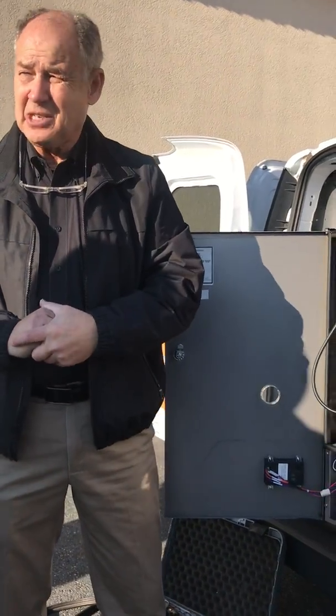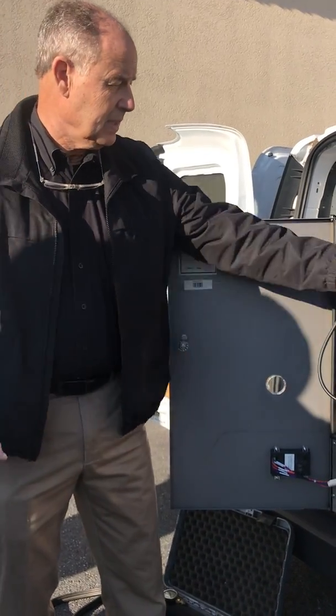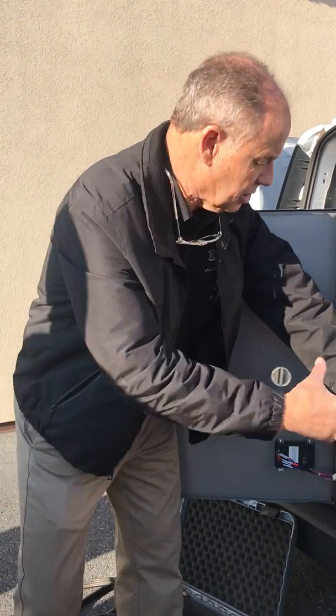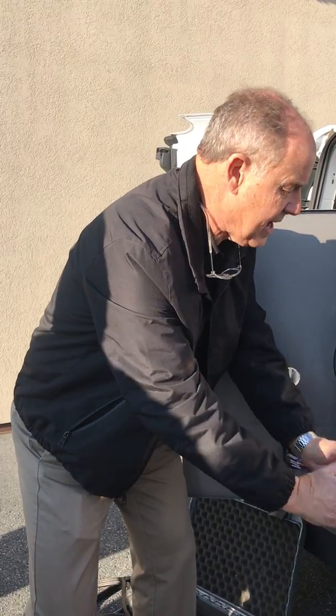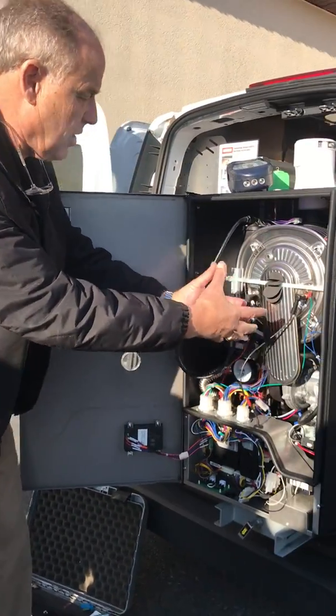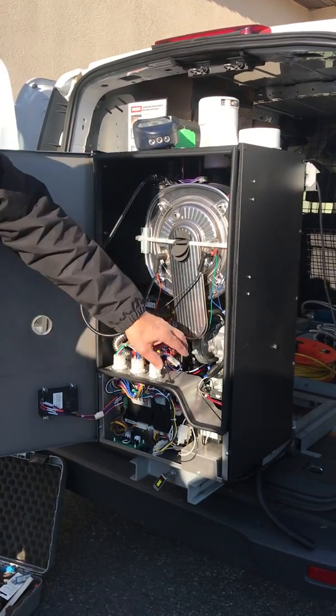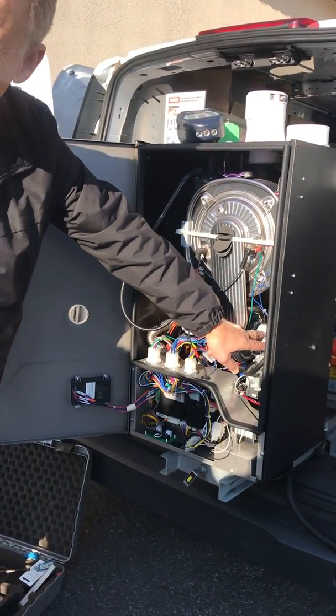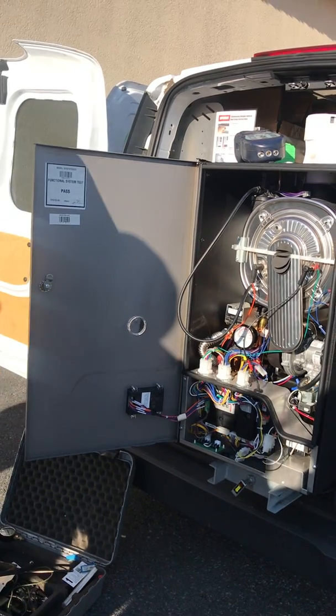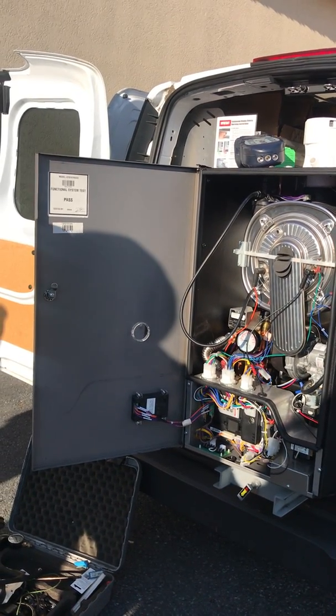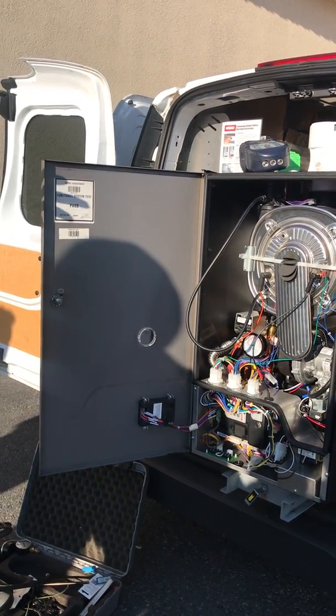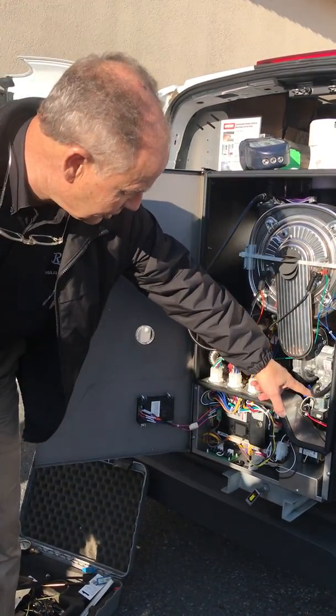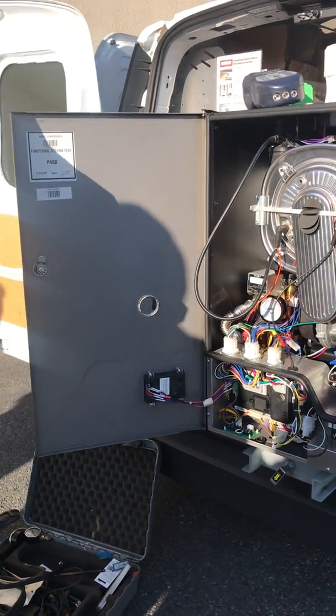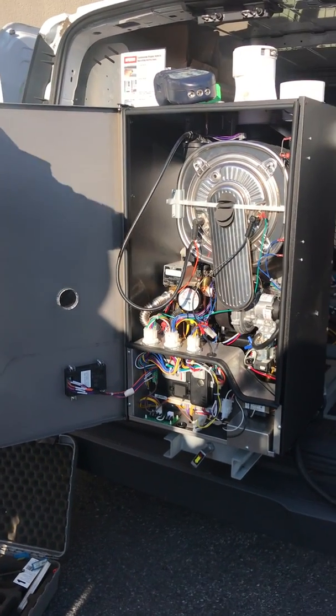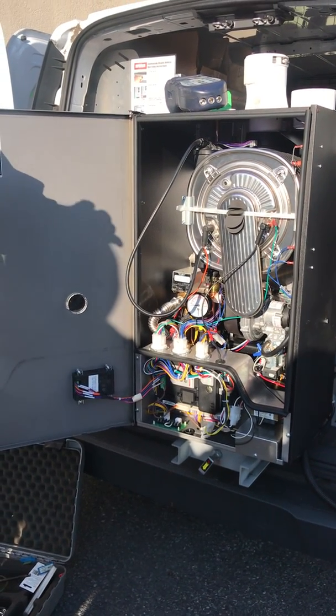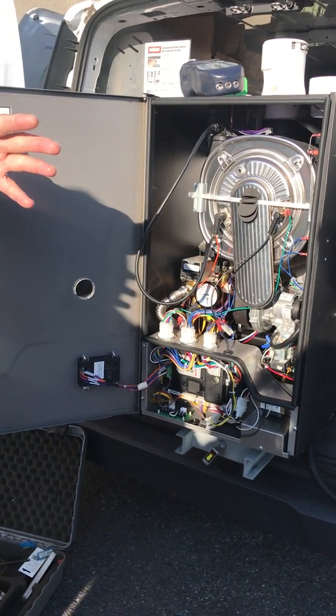But when you get a job and you need to convert it from natural to propane, these 4 nuts are going to come out. You're going to loosen the union. The nut's going to drop down. I can take all my wires off and I can pull this whole thing out. We're going to change this little venturi right there. Now, if you do like all the contractors do, read the manuals and follow their instructions, they're going to tell you to take that throttle screw and screw it all the way in and bottom it out and take it out so many turns. I'm telling you, don't do that. Just put the new part on and light it.